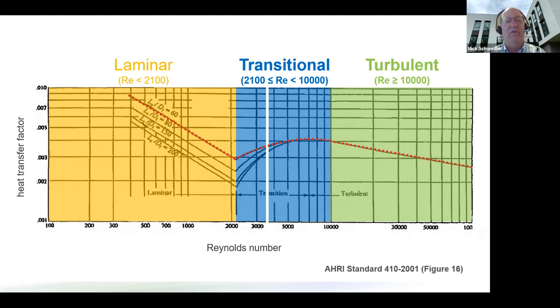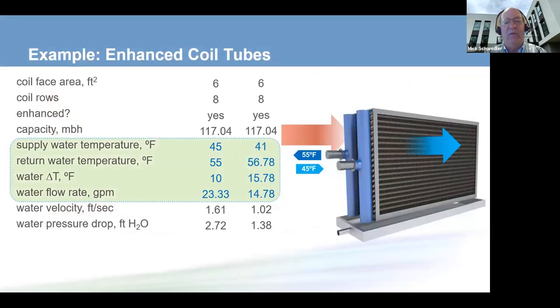But what we need to do is avoid this transitional point in the coil selection. If you have an existing coil, you can go to the manufacturer, ask them to reselect the coil with colder chilled water temperature and see whether that coil can work well. There's another way you can also enhance the tubes and their heat transfer. It's a way to keep you above that transitional range. In this case, with that 41 degree water, we went almost up to 57 degree return water temperature again. And so we were able to take that small coil with the enhanced tubes and increase its heat transfer capabilities.